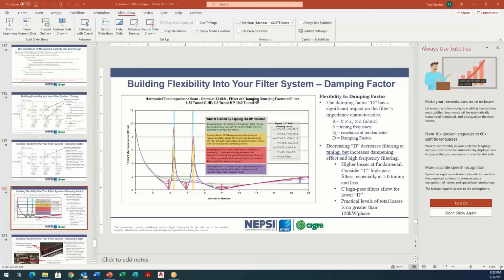My experience is that in South America so far, and also in North America, minus Quebec, which is one of the eastern provinces of Canada, capacitor banks are most often being utilized. The developers are staying as far away from filters as they can because of cost. In Quebec, the interconnecting utility defines an impedance loci, and because of the way they define it, those wind farm developers are often pushed into developing a harmonic filter for their projects.